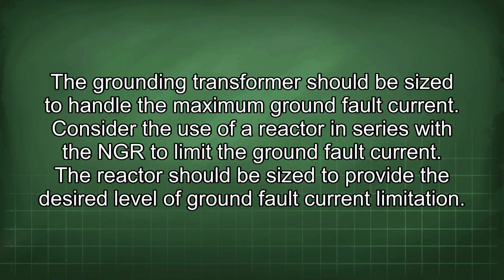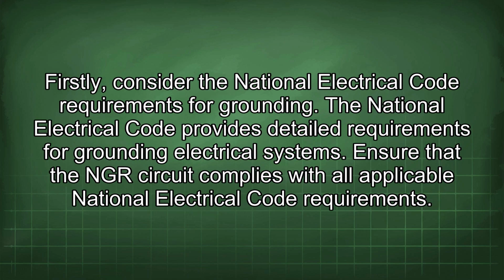Consider the use of a reactor in series with the NGR to limit the ground fault current. The reactor should be sized to provide the desired level of ground fault current limitation. Firstly, consider the National Electrical Code requirements for grounding. The National Electrical Code provides detailed requirements for grounding electrical systems. Ensure that the NGR circuit complies with all applicable National Electrical Code requirements.